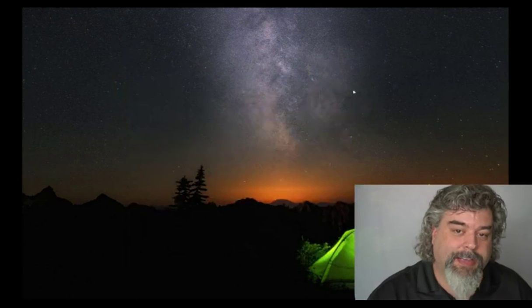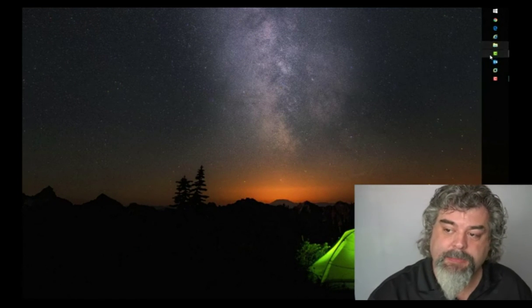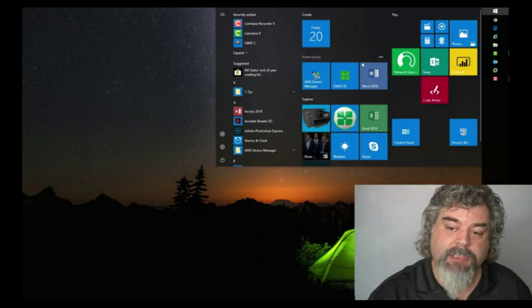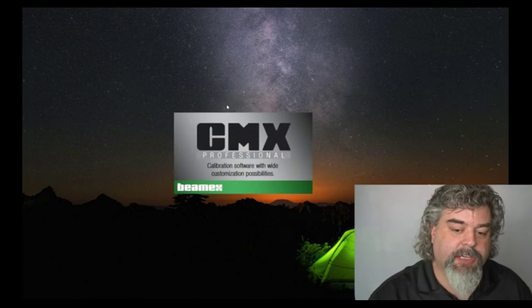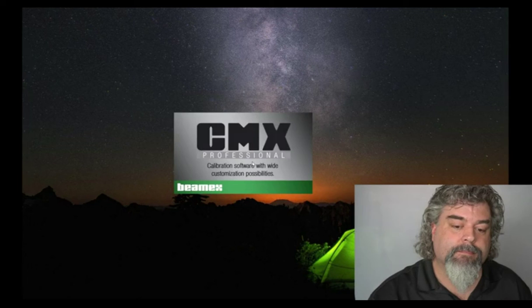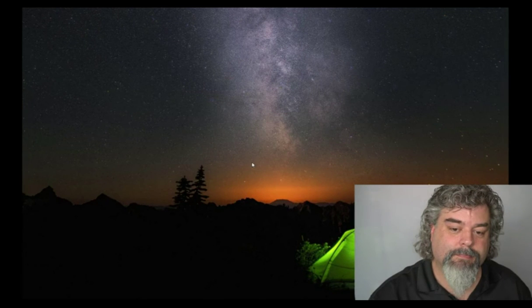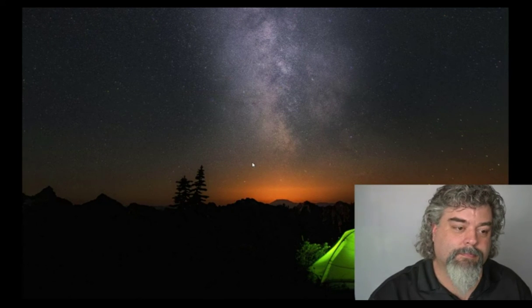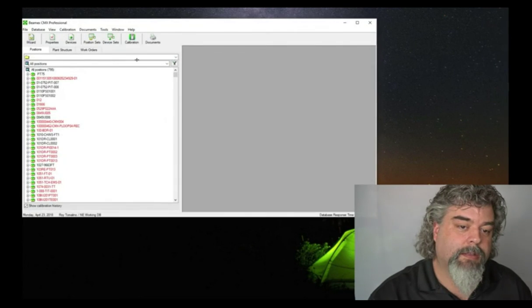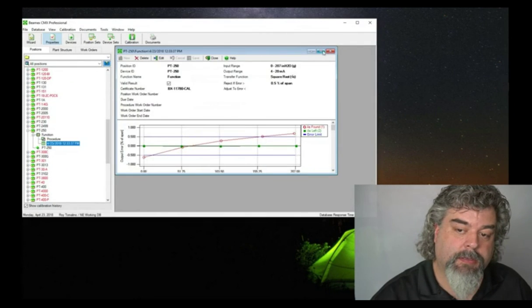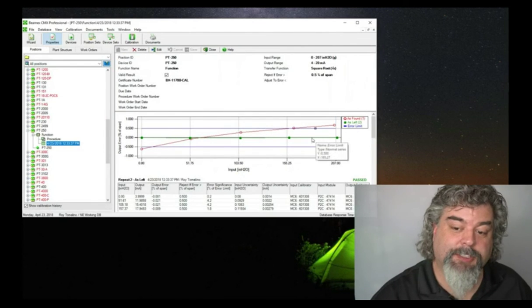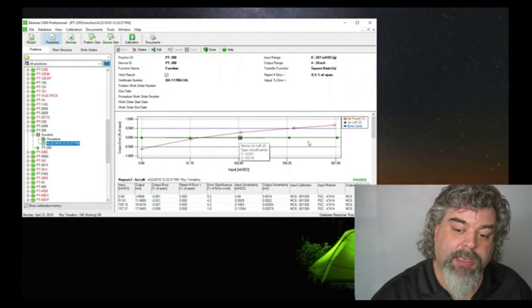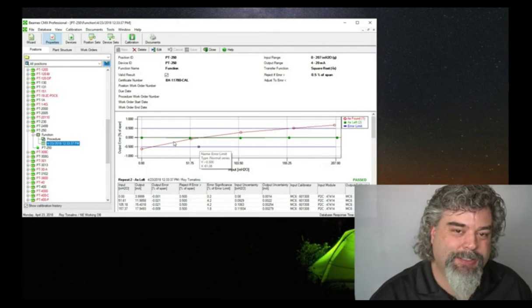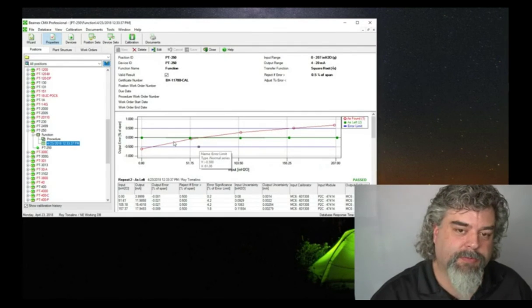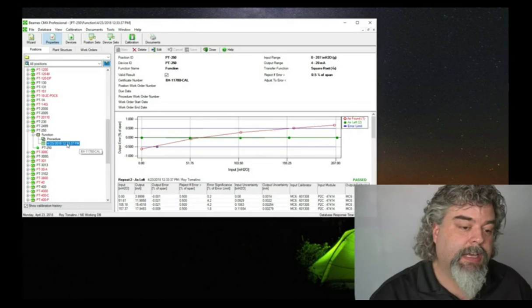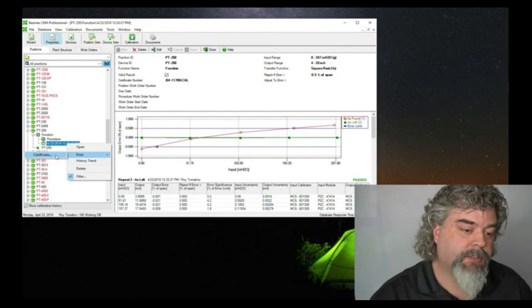Now let me do this. I'm going to close this out and actually unload it so we have a complete document. And I'll fire up CMX, the calibration software. Here's my test result. So this is what it looks like. The red is from when we started, and the green is how we left it. So if you're being audited or you need to give this info to a supervisor or maybe quality, I would do this. Right click it and go to print certificate.